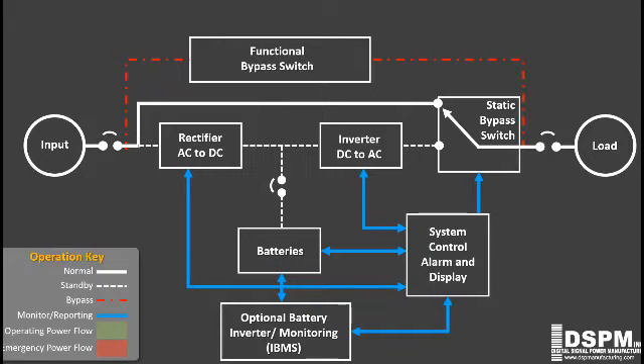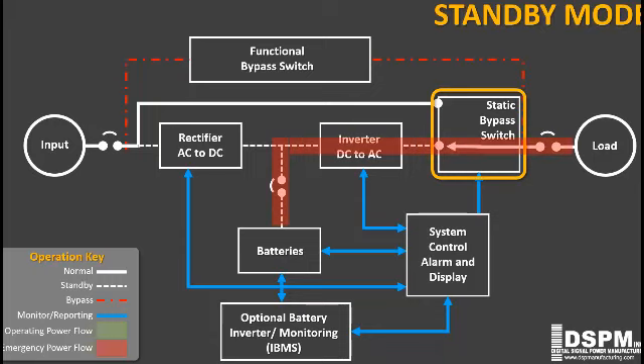At first glance, DSPM standby inverters look similar to our online inverters. The only difference is how power flows through our standby inverters. Basically, during operation, illustrated by the green line, the delivery of power to your load is directly from the utility provider to your load controlled by the solid-state bypass switch. In the event of a power failure, illustrated by the red line, the static bypass switch quickly and seamlessly transfers to the standby batteries in 4 milliseconds or faster when needed.